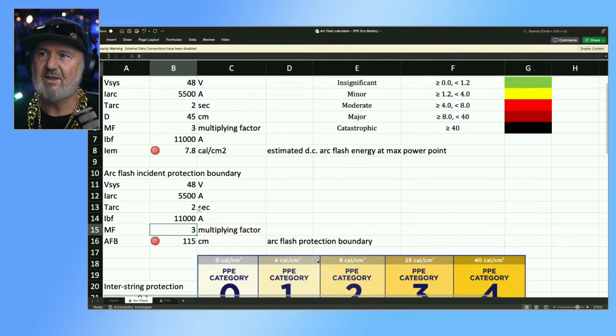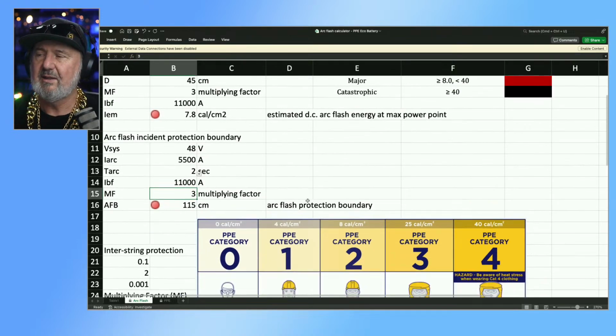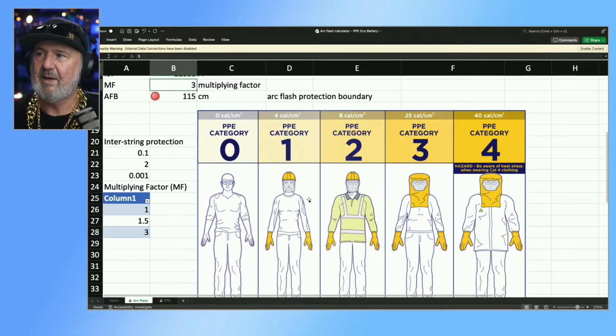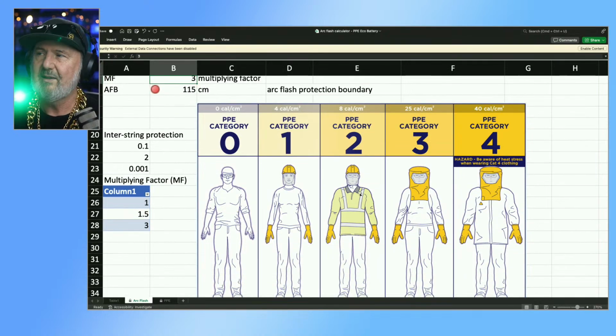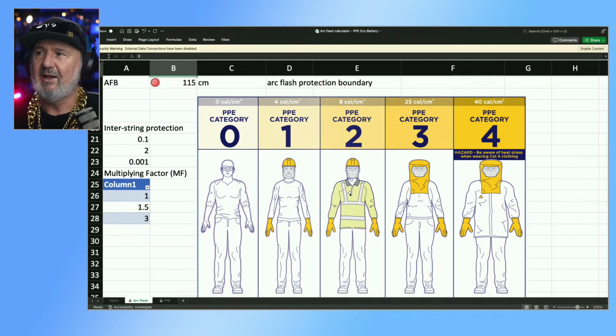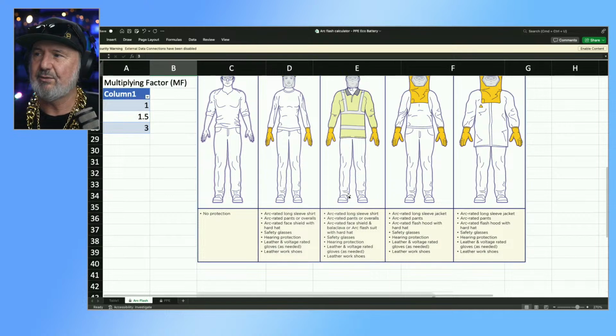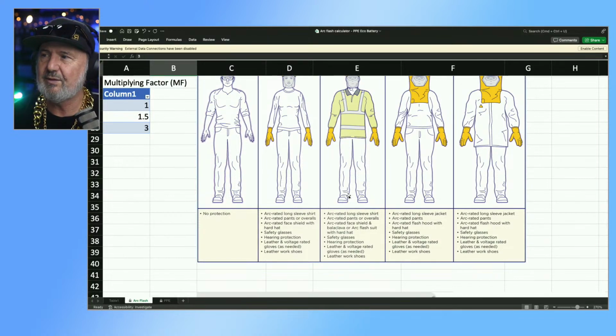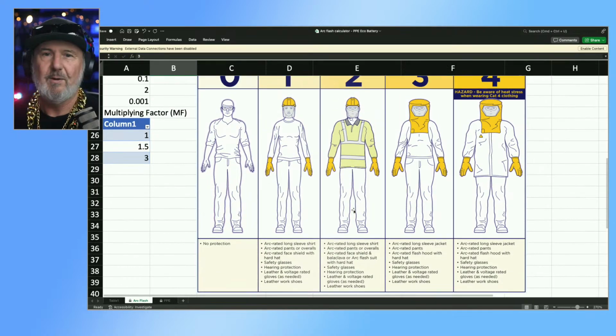So if we go down here, this is a 7.8 cal fault current. So we're basically looking at category 2. So up to 8 cal, between 4 and 8 cal, we're category 2. So that's quite a lot of kit on. Arc-rated long-sleeve shirt, arc-rated pants, overalls, arc-rated shield, balaclava, hard hat, safety glasses, hearing protection, leather and voltage-rated gloves, leather work shoes, just to top up the water in your lead acid battery. You try and explain that to a customer.